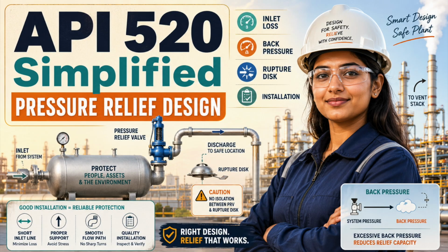The discharge system must be evaluated from the valve outlet through the tailpipe, fittings, subheader, main header, knockout vessel, and final disposal point. Do not check only the first few meters of pipe. The valve experiences the resistance of the complete connected system. Rapid depressurization can also produce severe cooling. Auto refrigeration may lower the temperature of the valve outlet, tailpipe, and header enough to create brittle fracture concerns. Normal operating temperature is not the only material selection basis.